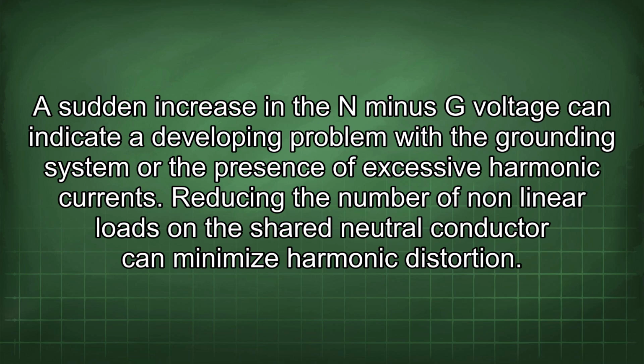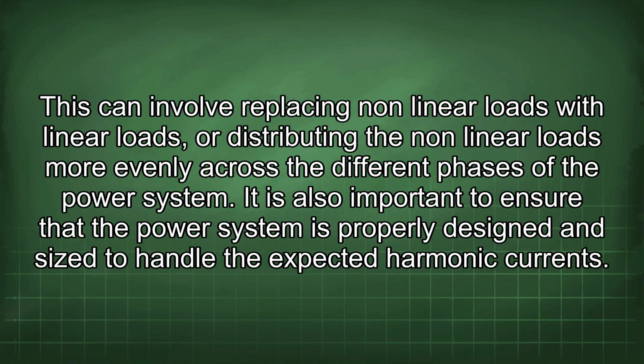Reducing the number of nonlinear loads on the shared neutral conductor can minimize harmonic distortion. This can involve replacing nonlinear loads with linear loads, or distributing the nonlinear loads more evenly across the different phases of the power system. It is also important to ensure that the power system is properly designed and sized to handle the expected harmonic currents.